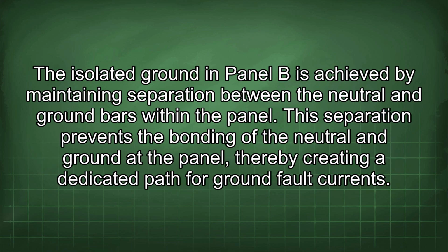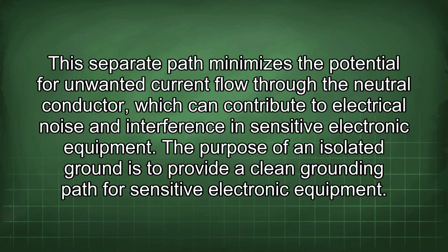The isolated ground in panel B is achieved by maintaining separation between the neutral and ground bars within the panel. This separation prevents the bonding of the neutral and ground at the panel, thereby creating a dedicated path for ground fault currents. This separate path minimizes the potential for unwanted current flow through the neutral conductor, which can contribute to electrical noise and interference in sensitive electronic equipment.